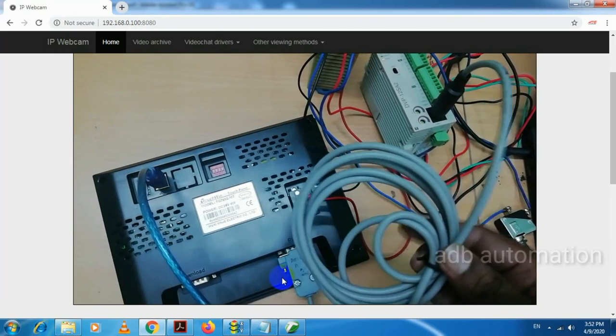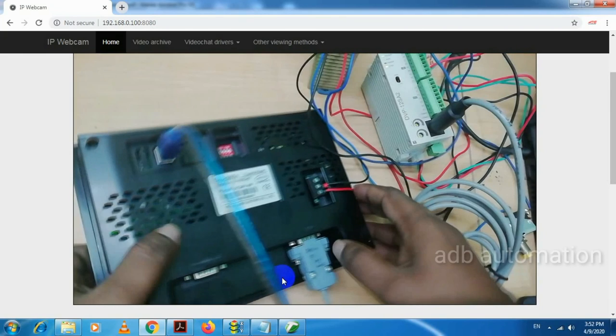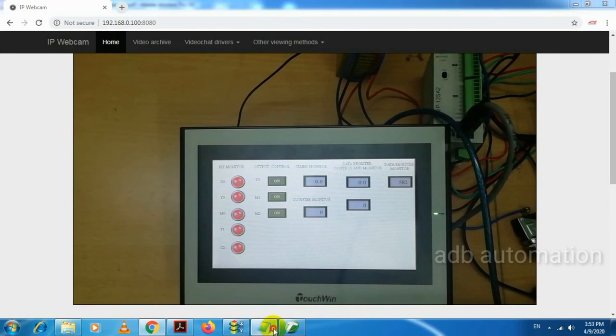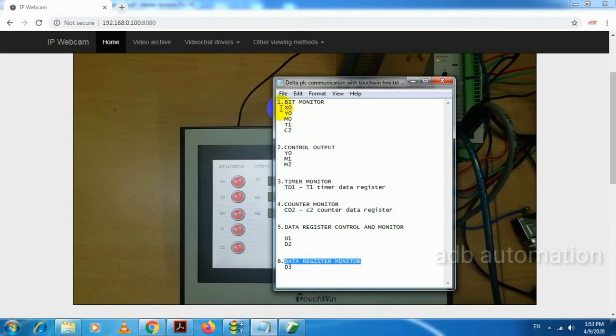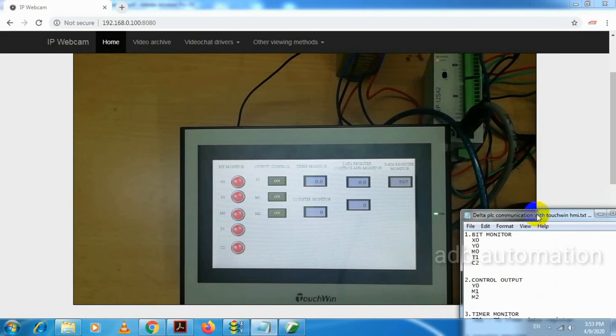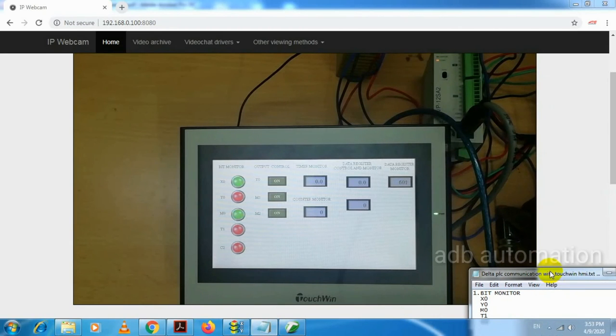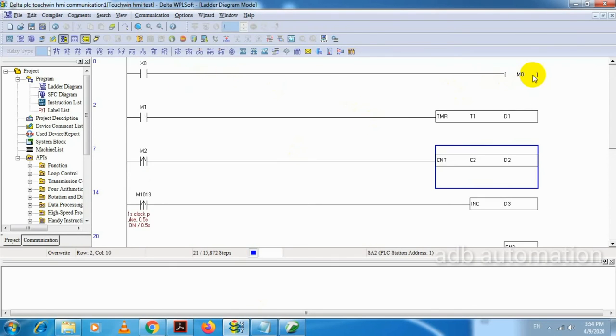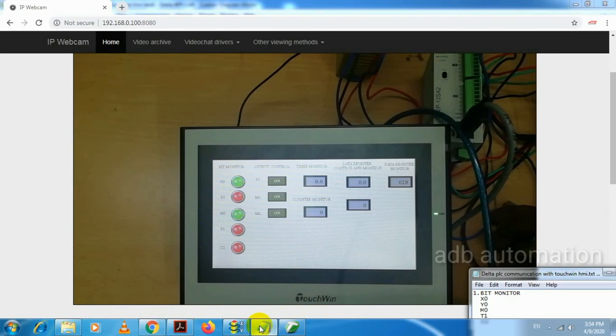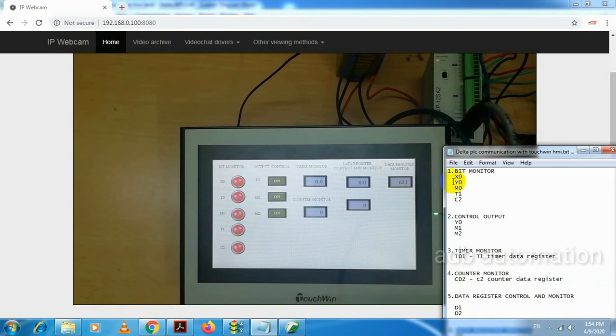Now we will check our program. First we have to check the bit monitor — we need to monitor X0, Y0, M0, T1, and C2. I have connected a push button to X0, so I will press this push button. X0 is on. In the program, X0 is connected to M0, so if X0 is on, M0 will also get on. That logic is working here.